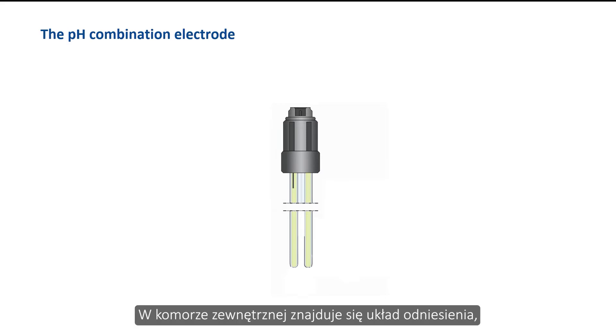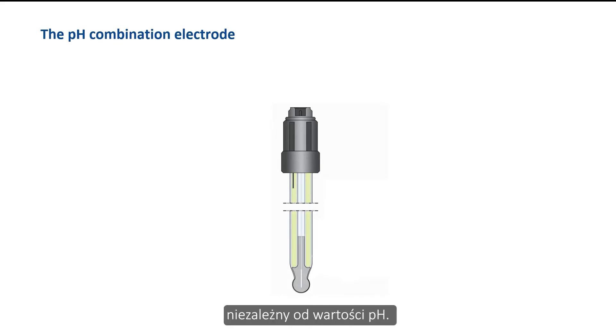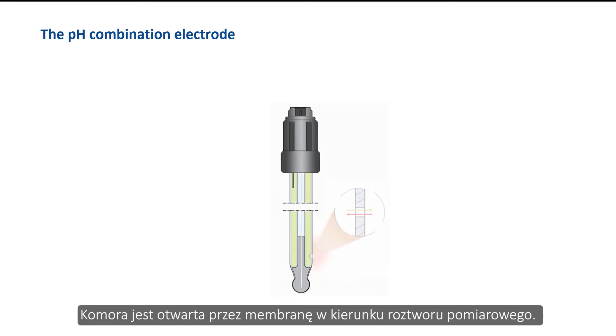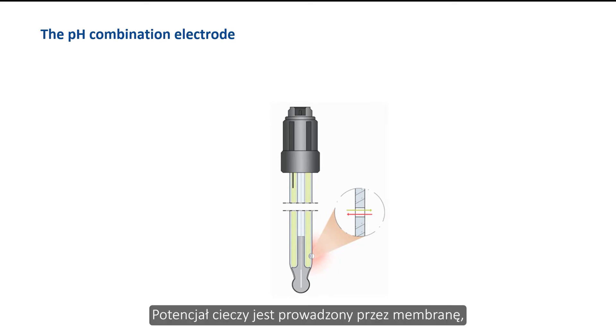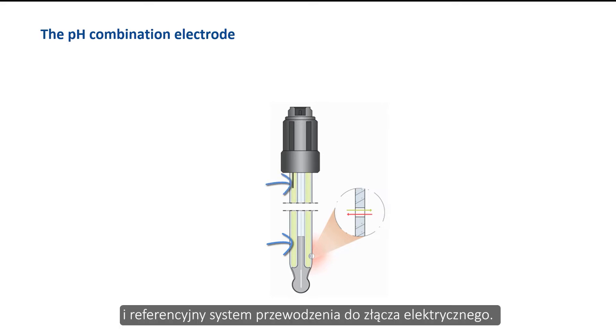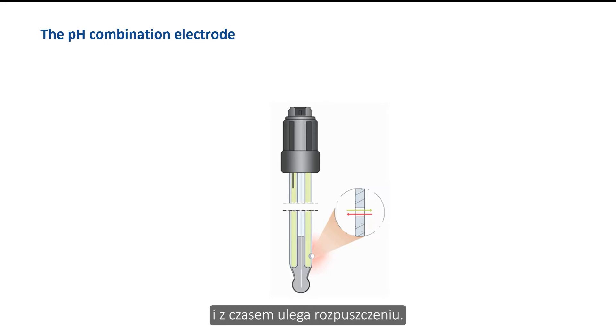The outer chamber contains the reference system, which provides a stable reference potential independent of the pH value. The chamber is opened through the diaphragm towards the measuring solution. The liquid potential is led through the diaphragm, the reference electrolyte, and the reference conduction system to the electrical connection. The reference electrolyte consists of saturated potassium chloride and dissolves over time, which is why combination electrodes should be regarded as consumables.